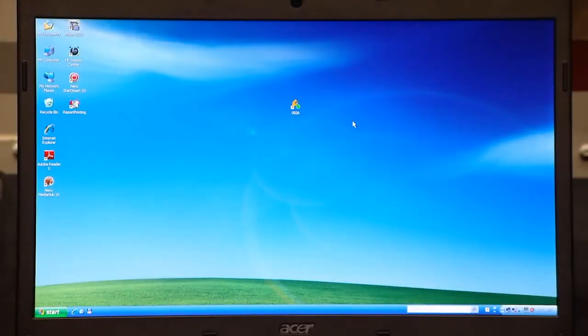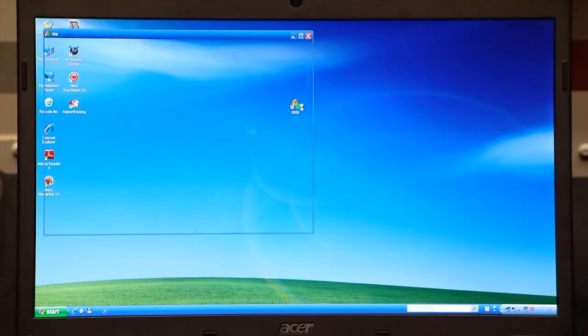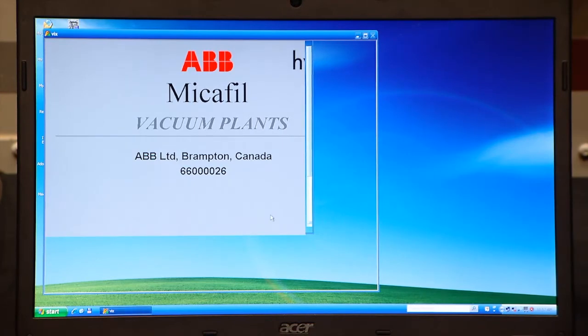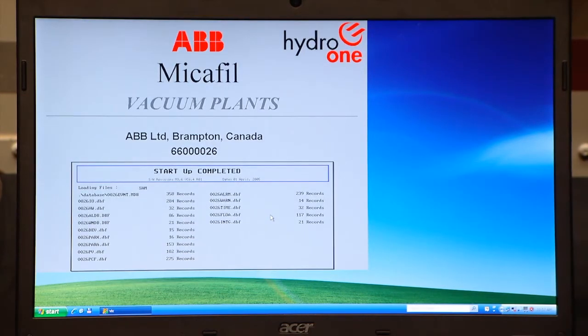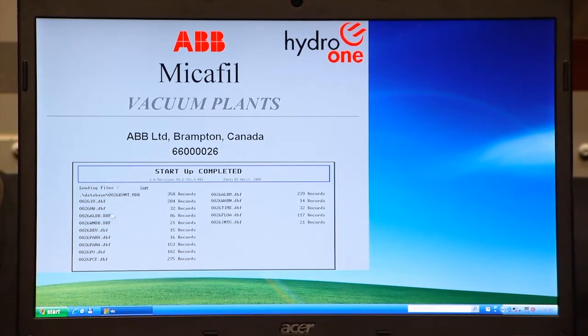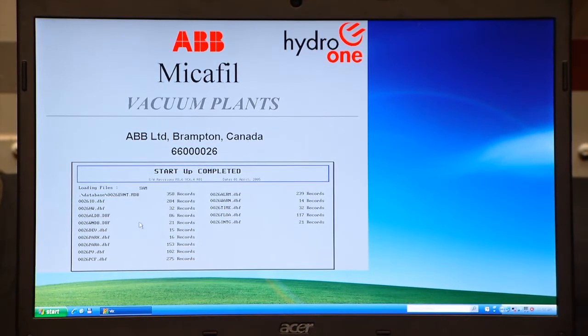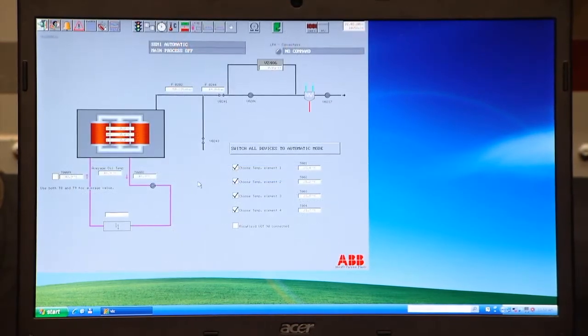We are here now at the startup, and starting the computer, you will have an icon on the desktop which says the product number. You double click that one and the system starts up. You will then have your startup screen. Important to notice if all the databases have some records, or if you see any errors out here. If you do, then you might have an issue to get all the recordings and so on properly done. Click anywhere, you come to the first page showing the transformer with its temperatures.